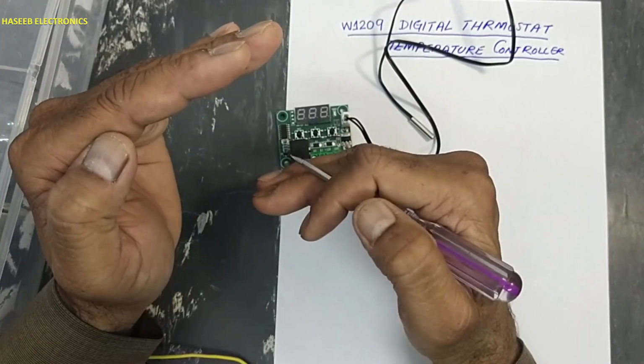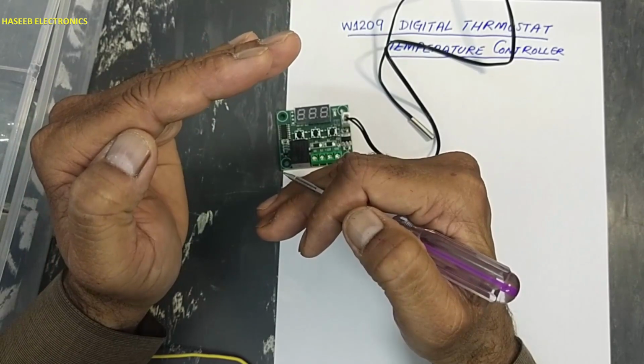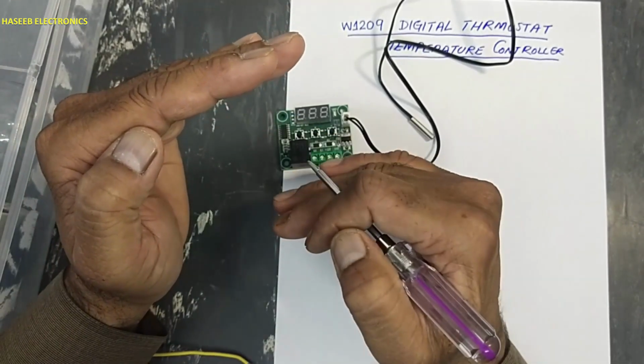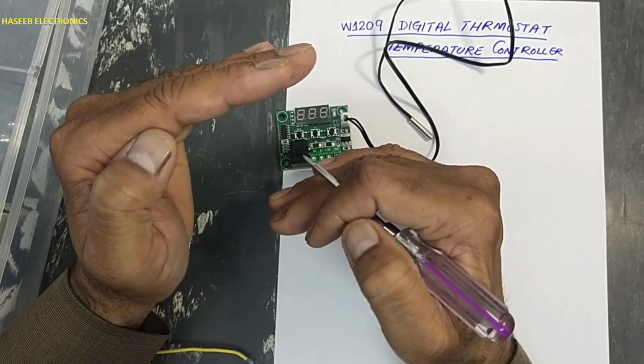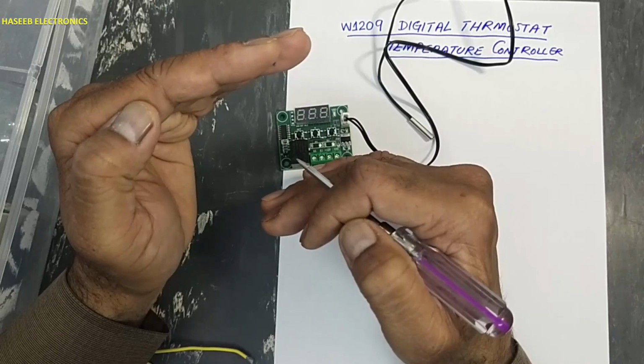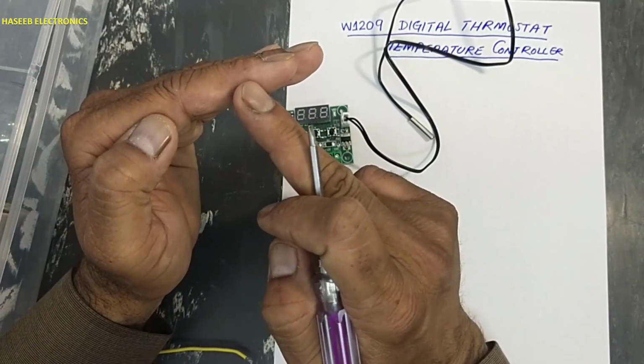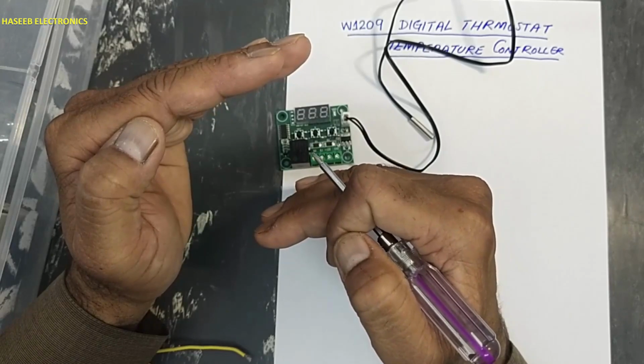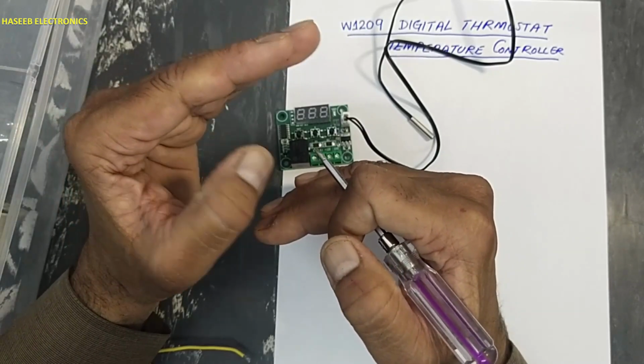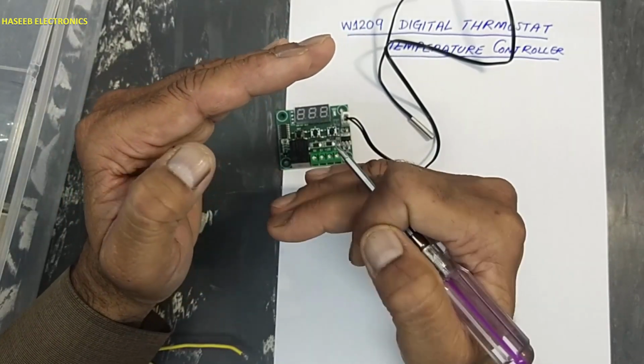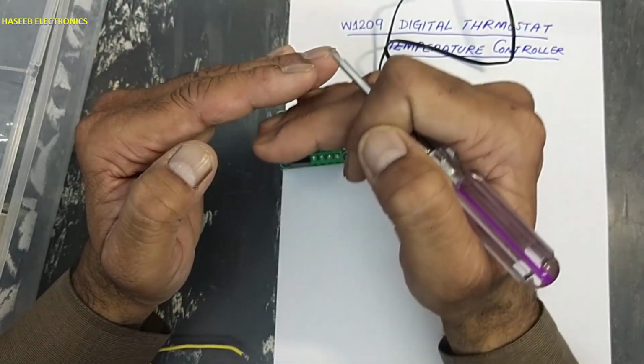We will set an upper limit temperature and a backlash temperature. So between these two limits, it will turn on the heater to maintain the temperature within this window. Let's suppose 35 degree upper limit, backlash temperature 2 degrees, 35 minus 2 degrees, 33. At 33 it will turn on the heater and it will reach up to 35.